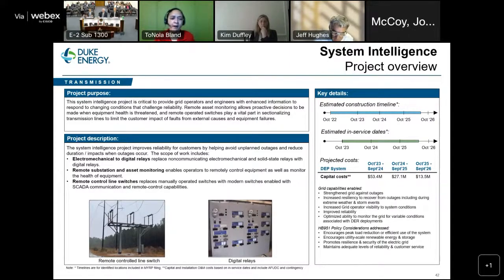This condition-based monitoring technology uses an inline gas meter analyzing potential fault gases accumulating in our critical power transformers, sending that information to our engineers and subject matter experts so they can decide how long until a transformer fails, or when to take it out of service to proactively inspect it or do additional maintenance. That's our asset monitoring program.